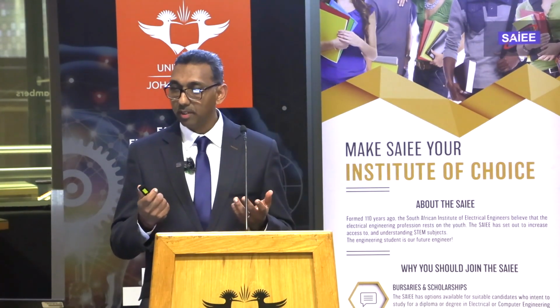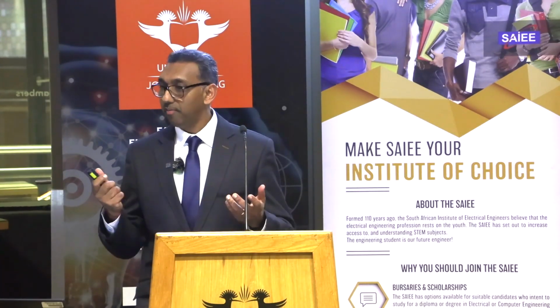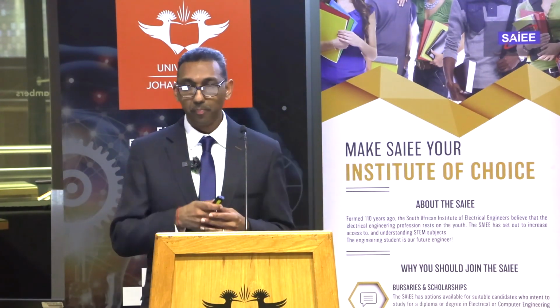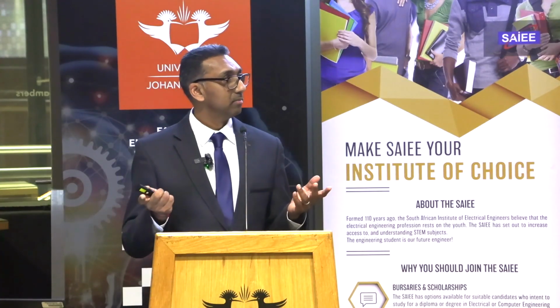The next challenge - I want to jump to the OCGTs. If we look at their maintenance, we have this equation, EOH, equivalent operating hours. When we reach a certain level, we have to do certain maintenance. It's based on the number of starts, fast loading, fast temperature changes, fuel factor, hours running in base load, and hours running in peak load. But the way our OCGT units have been operated and run in this country - not around the world, only here - is where we stop and start them. It's essentially insurance.